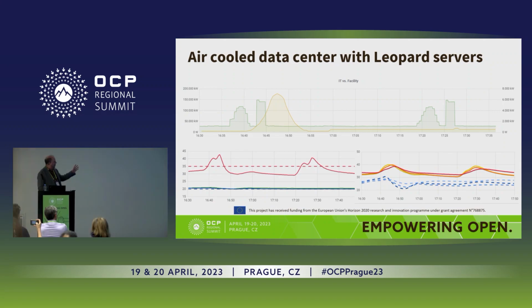So on the left there, you can see the IT workload. We use a synthetic workload, so we pushed on a V-shaped workload. It went up to 110 kilowatts from an idle power of about 25 kilowatts. And then we put a large square wave on it to a peak of 150 kilowatts. What you can see with the yellow line is the actual workload, and the red on the right-hand side is the power consumed by the coolers.